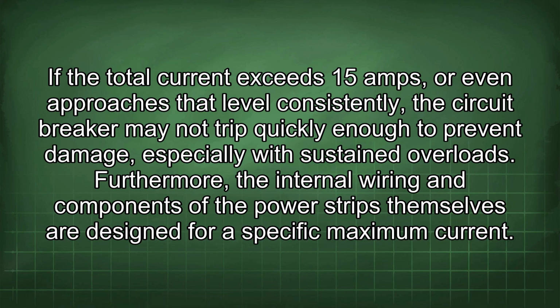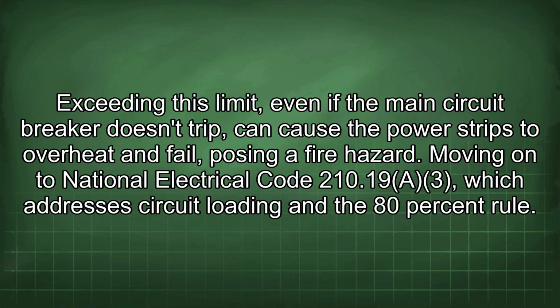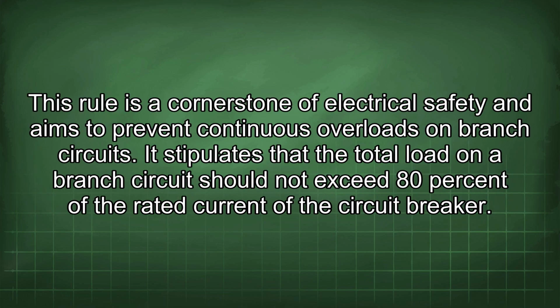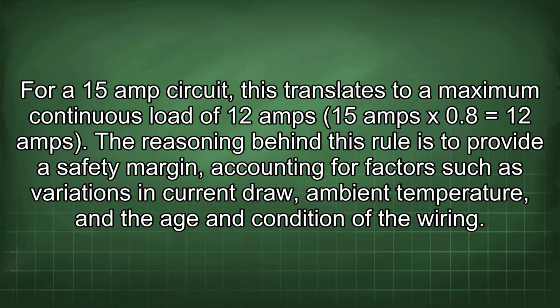Furthermore, the internal wiring and components of the power strips themselves are designed for a specific maximum current. Exceeding this limit, even if the main circuit breaker doesn't trip, can cause the power strips to overheat and fail, posing a fire hazard. Moving on to National Electrical Code 210.19(A)(3), which addresses circuit loading and the 80% rule. This rule is a cornerstone of electrical safety and aims to prevent continuous overloads on branch circuits. It stipulates that the total load on a branch circuit should not exceed 80% of the rated current of the circuit breaker. For a 15 amp circuit, this translates to a maximum continuous load of 12 amps.